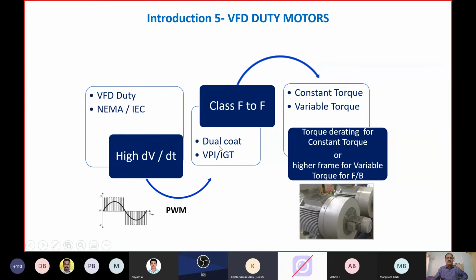Dual coat means polyamide winding wire instead of the polyester winding wire available in the market. So dual coat winding wires, followed by impregnation in vacuum pressure. Instead of dip and cure, it should be vacuum pressure impregnation, or inverter grade treatment, to make the motor fundamentally eligible to be called a VFD duty motor.